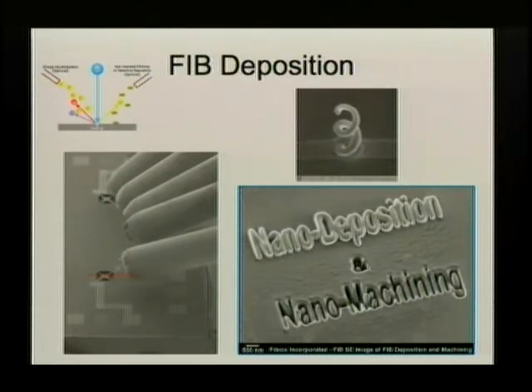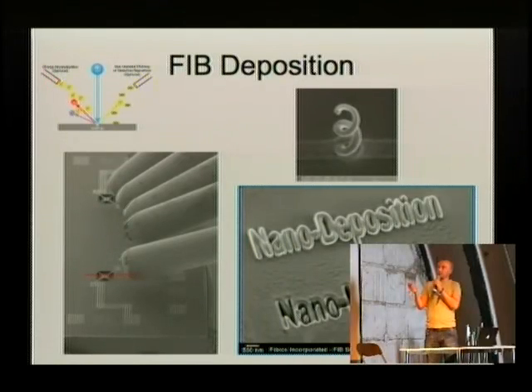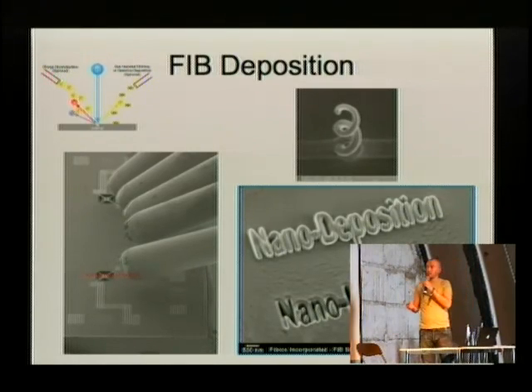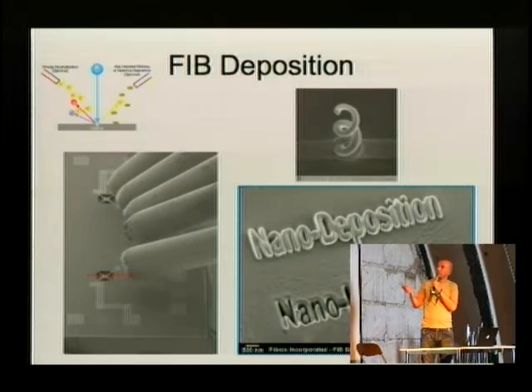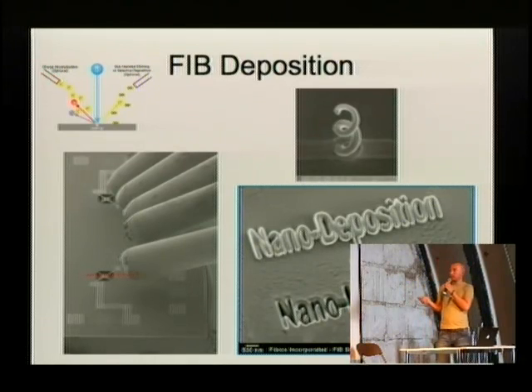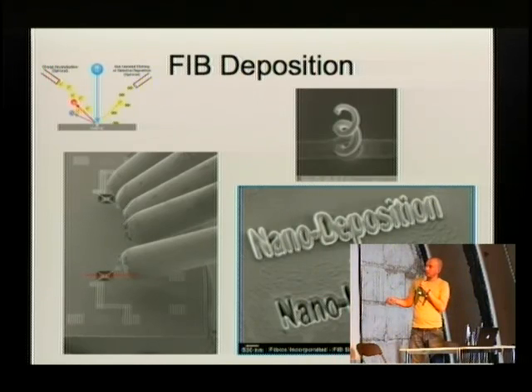There's another thing we can do with the FIB, and that makes it even more interesting than the milling. If we inject some gas into the chamber with a small needle, normally you use some sort of carbon compounds that bind to a metal or an insulator. You can deposit the material onto the surface. The chemical bonds inside these carbon compounds get broken up by the ion beam, and you can locally deposit material.